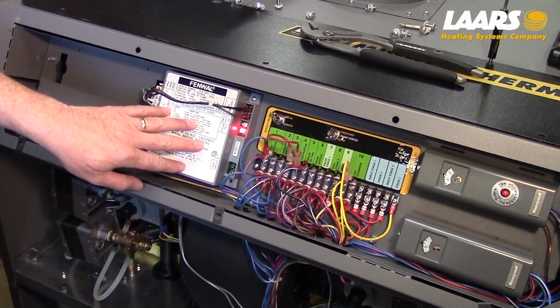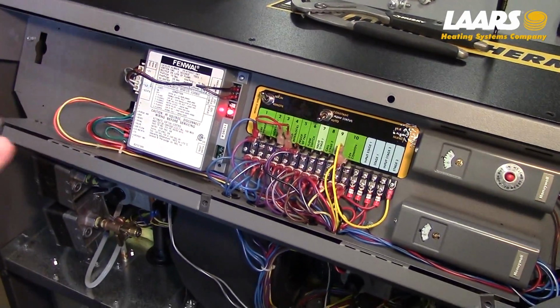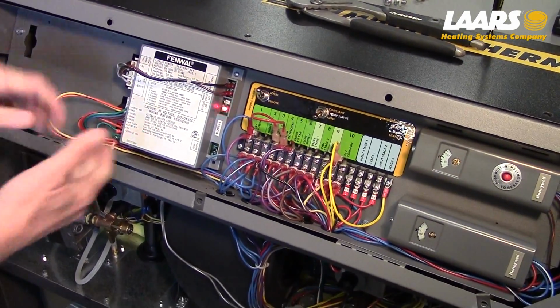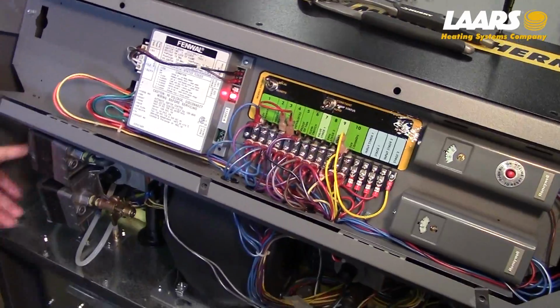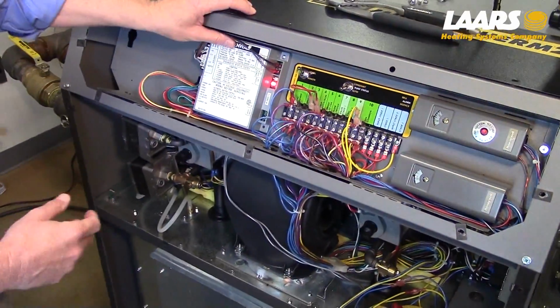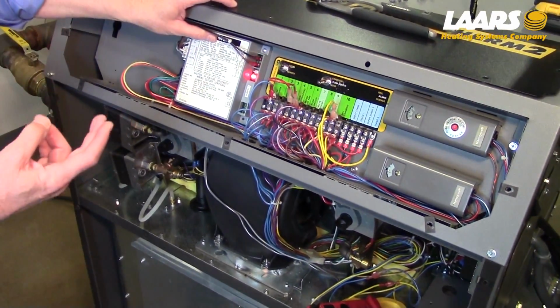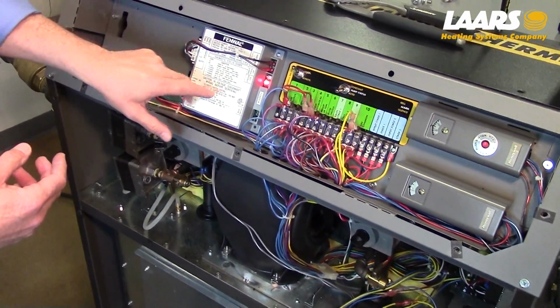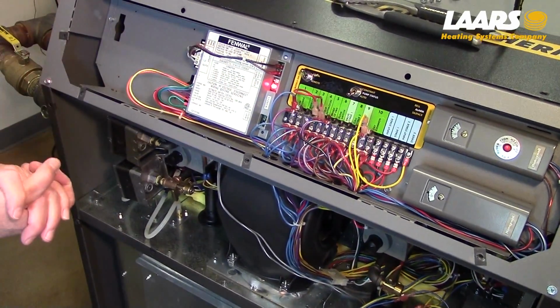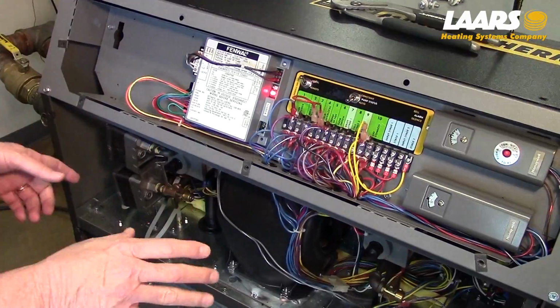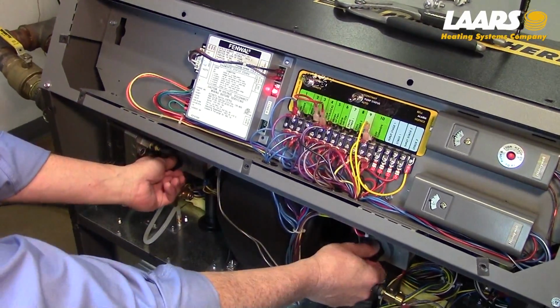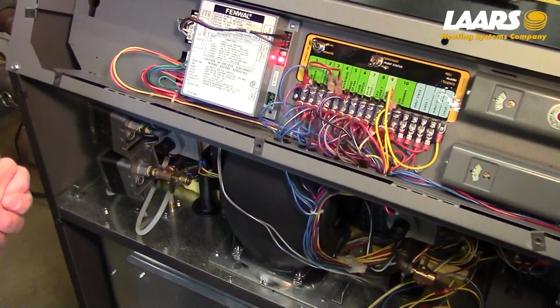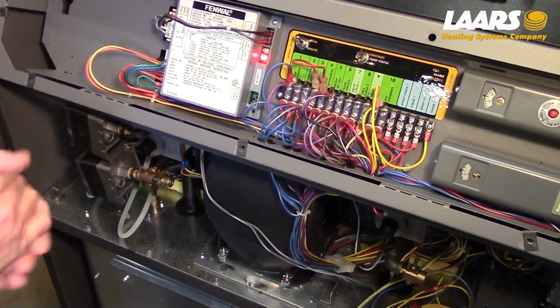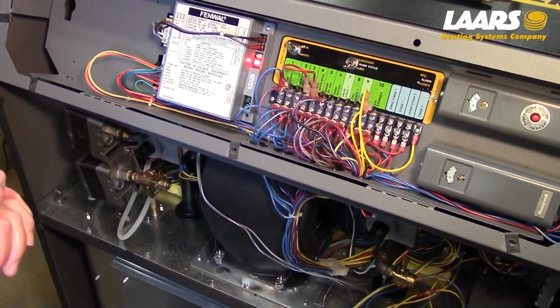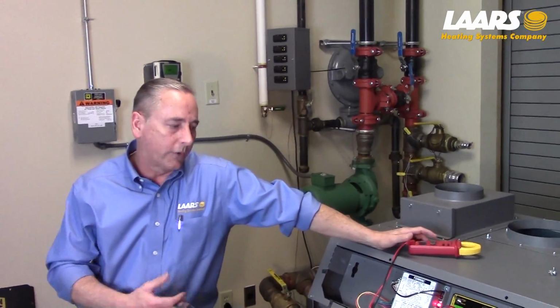On CSD1, it'll only be a single try for ignition, and that's certain safeties that we would have, high-low gas pressure switches, low water cutoff, etc. On a non-CSD1, would be 3 tries for ignition before it shows a hard lockout. And what I did to simulate this was I very simply shut off the gas valves, and that way I was able to test the igniter and put it into a trouble fault. So that's a very simple test to walk through the safety chain.